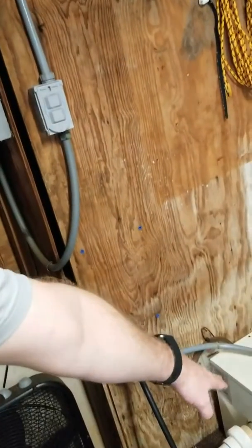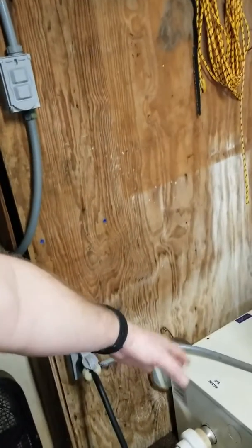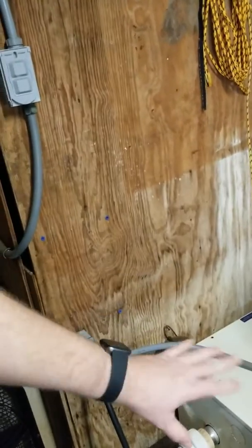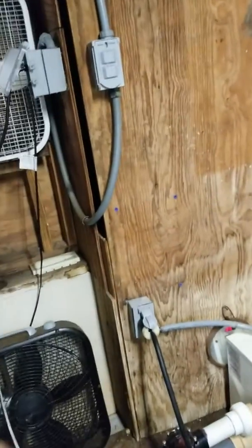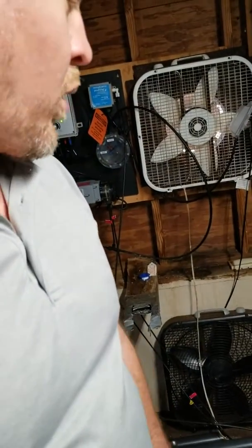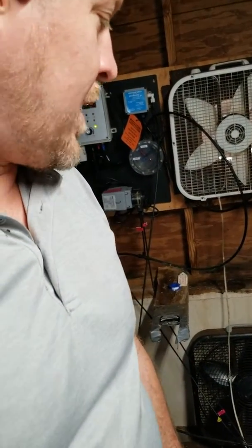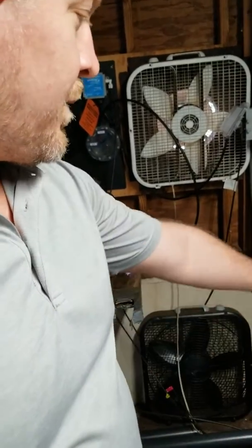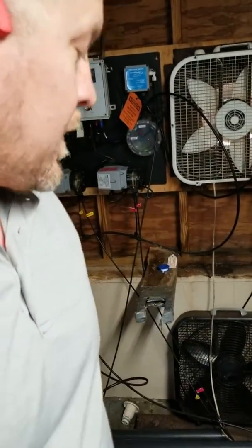Also, their heater is not coming on. So it's getting power. I've already looked in it. It's got a bad contactor, but we do have water coming from it. So what I would do with this report is report it as a plumbing issue. They've got a leak on the heater. They're missing gauges and labels and flow meters.